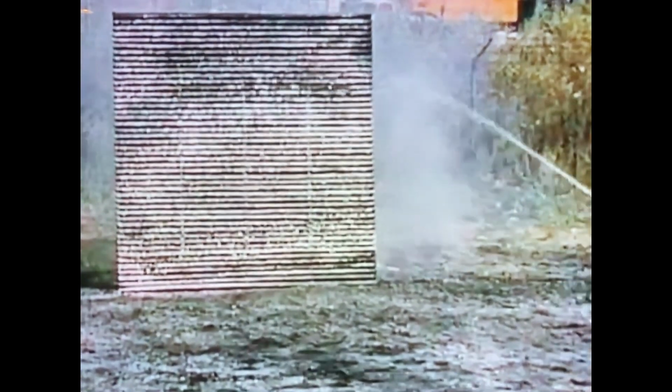A soda acid extinguisher can be used the same way too. All three, water, foam, and soda acid, come in similar containers and are applied in the same way on Class A fires. Regardless of which extinguisher you use, make sure the fire is out. Saturate each questionable spot to prevent a rekindled fire. Remember, there's no way to save the fluid in this type of extinguisher, so use it all to make sure the fire is out.